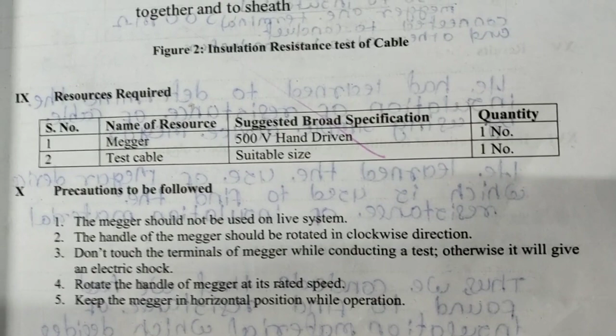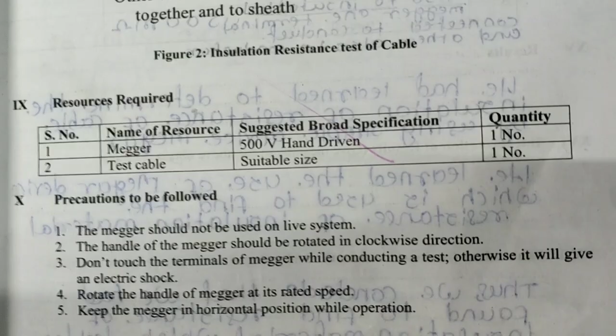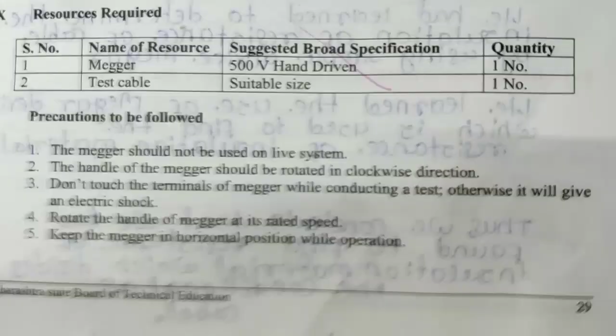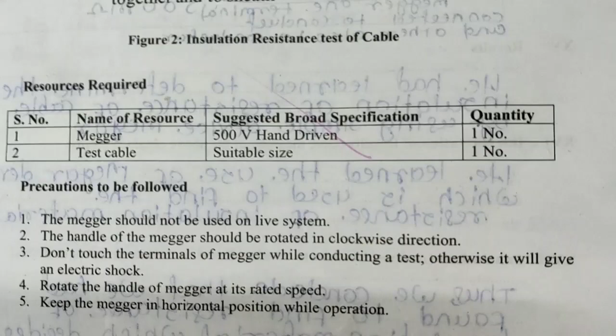Now you want to perform this practical by following some precautions. So, precautions to be followed. The Megger should not be used on a live system. Means the system is live, voltage is there in the conductor and current is flowing, and at that time you shouldn't use the Megger to test insulation resistance.